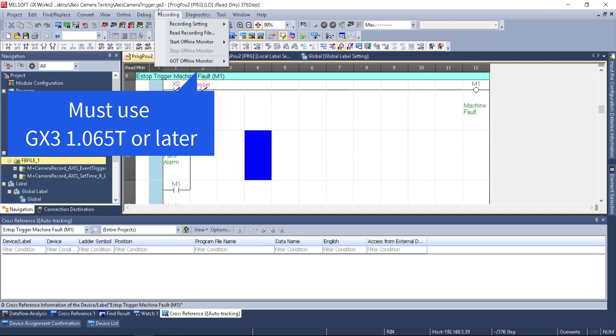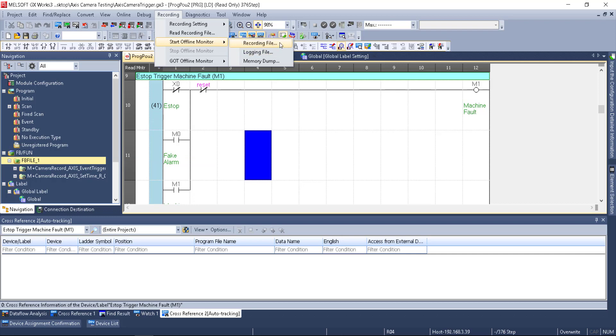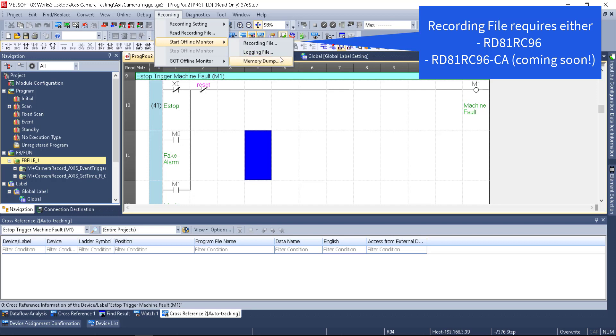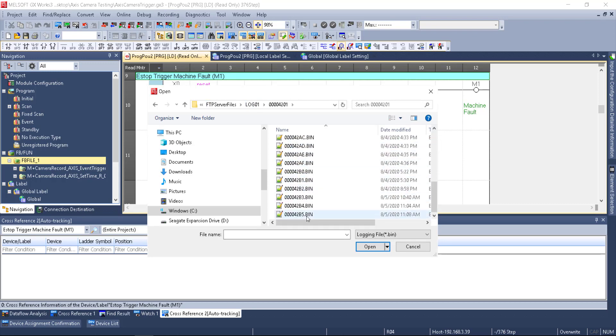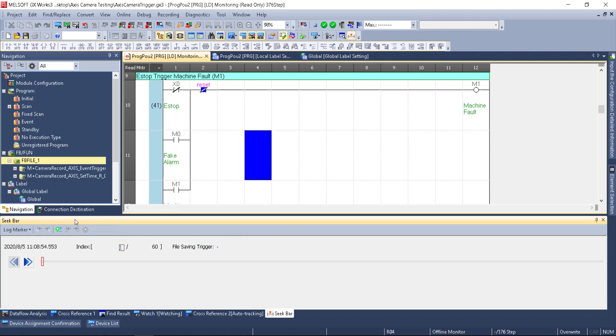Now let's look at GX Works 3. There's a new recording tab — brand new for GX Works 1.065. We start offline monitor, which is the main function. Offline monitor with a recording file would be for the recorder module or camera recorder module capturing 100% of all devices and labels. Since we don't have that, we choose logging file — memory dump gives all standard devices at one point in time, but logging file is recommended. We go to our logging folder, find the last binary file, double-click, confirm, and come up with a seek bar.